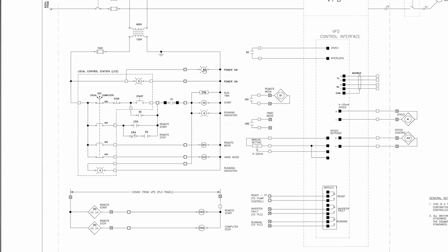These pumps were in the basement of this building, and the MCC was on the top floor, so that if there was a flood in the basement, you didn't flood out your high voltage. So these local control stations, they were downstairs right beside the pump. So if you needed to put the pump into local, off, or computer based on this drawing, or hand-off-auto, you could do that down at the pump, without having to go up and down the stairs a bunch of times. So power comes down, comes into this local off computer.